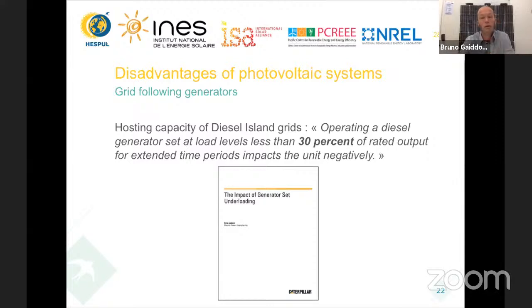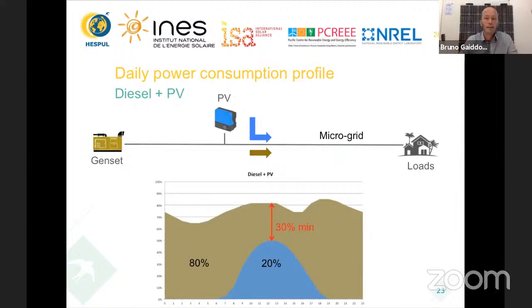If you know this rule, you now understand that there's a limited hosting capacity of the microgrid for PV. As you need to always run the genset at minimum 30% of its nominal power, you can't install as much PV as you want on a microgrid to keep it stable. On the generic load profile I showed you, if I want to install as much PV as I can, then I come to this limit, and over a day, I will only cover 20% of the daily consumption. This is more or less the limit that you have on a diesel microgrid with only a regular PV system. So you can't go above this limit.